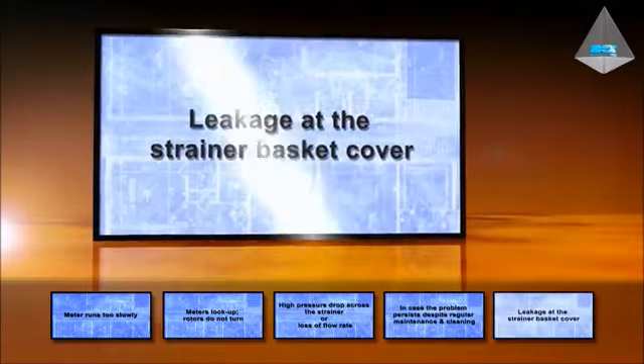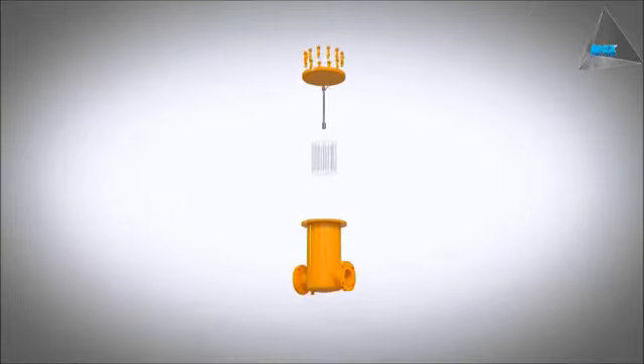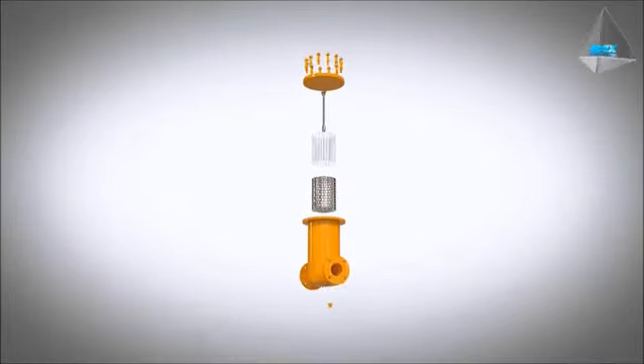Leakage at the strainer basket cover. Possible cause: O-ring or seals damaged due to ingress of dirt. Solution: replace the damaged O-ring or seals and clean the housing.